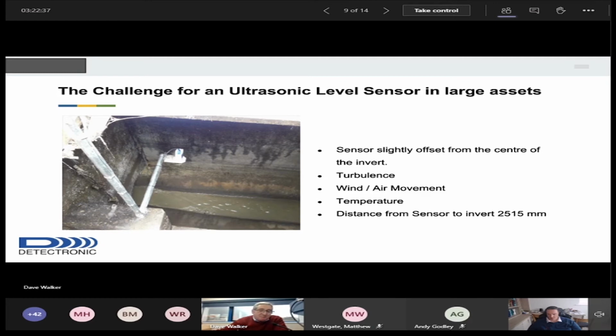Temperature, I'll touch on that in a bit as well, is a big issue with ultrasonic sensors. Now, that's something we all know a lot about, so we've got some very clever algorithms and signal processing to overcome that. And again, finally, distance from sensor to invert: you're near on its maximum range in this particular application. Hence the reason why that photograph you can see there, and that installation, is giving that data.